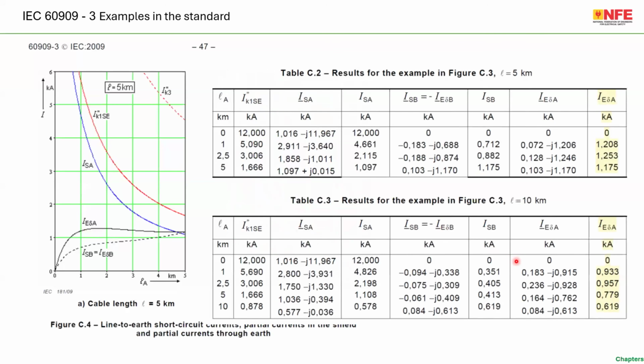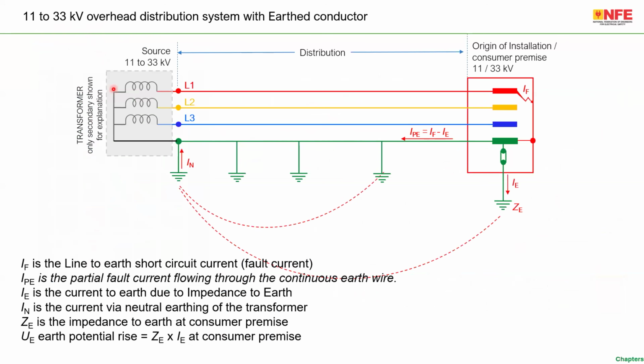What I wanted to tell you is, one mistake we always make is that we calculate the earth grid or earth electrode assuming that the fault current is 13 kiloampere, 50 kiloampere, 25 kiloampere, and so on. In the practical case, the earth electrode current, that means IE, is not that high. It is always very small, probably in the range of 1, 2, 3 kiloampere. It is never 50 kiloampere because the majority of the fault current is supposed to flow through the metallic fault return path. As an argument, if somebody wants, we can go to the standard 60909 part 3, have a detailed calculation and find out exactly what these values are.